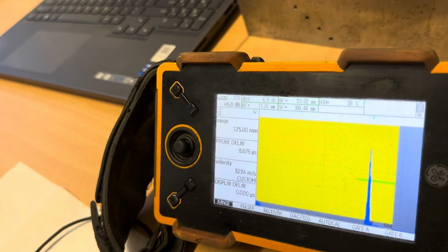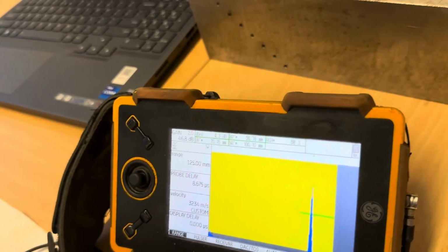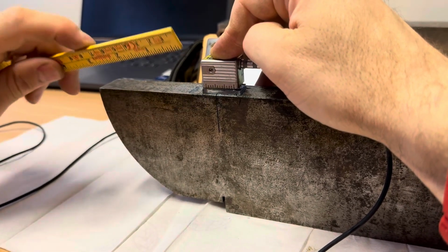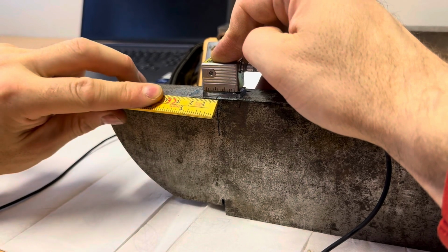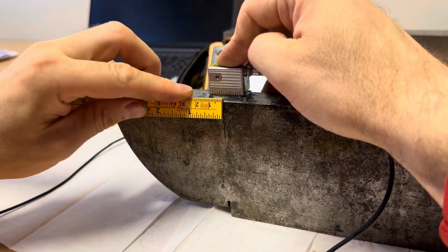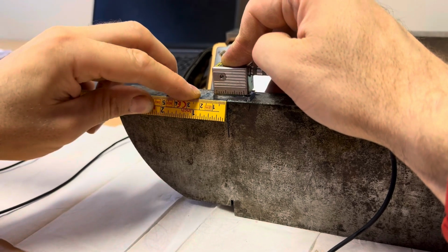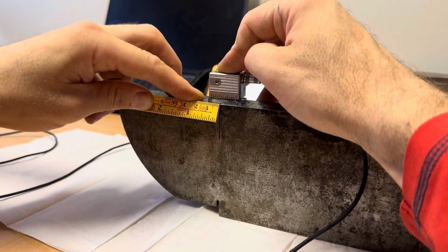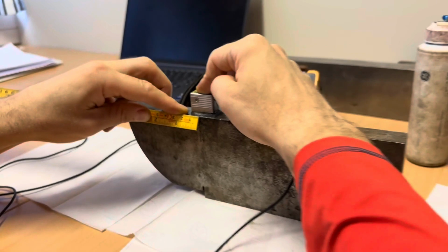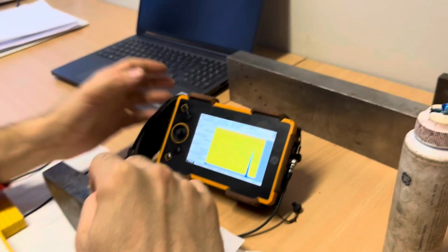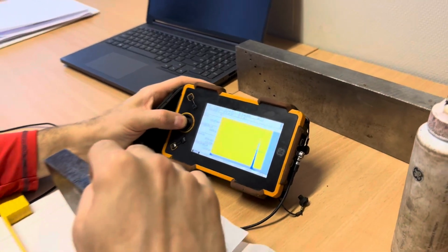We check on the sample itself, and also look at the caliper. We carefully look at the blocks where our mark is and measure, since here we simply measure the distance to the start of the sample. This will be 13 millimeters. We can measure more precisely if we imagine one more line. 13 millimeters. We go into the menu.